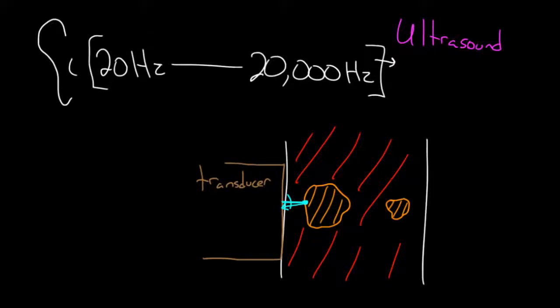And this transducer is always timing. It knows when it sent out the pulse, and it knows when that pulse got reflected back. It also knows the speed of sound, so it can calculate, all right, if it took that long to get back, it must have reflected this far away, something's at this point. And that's not done yet, though. Some of this wave is going to travel on. In fact, most of this wave keeps going. Here's another interface between tissue and blood, so it's going to reflect again. This reflects back. We'll get another pulse at some later time, and the transducer knows, all right, it took that long, so there must have been something else there. My one pulse got reflected two times. So there's something here, and here's the end of it.